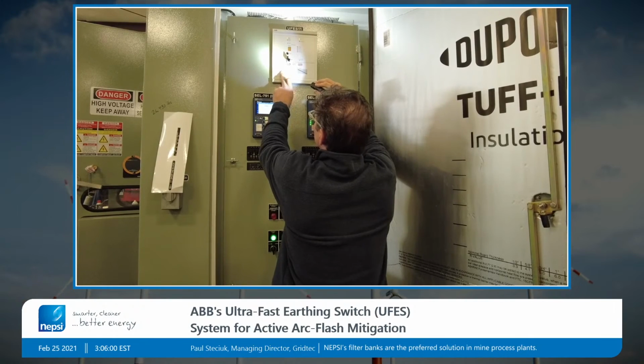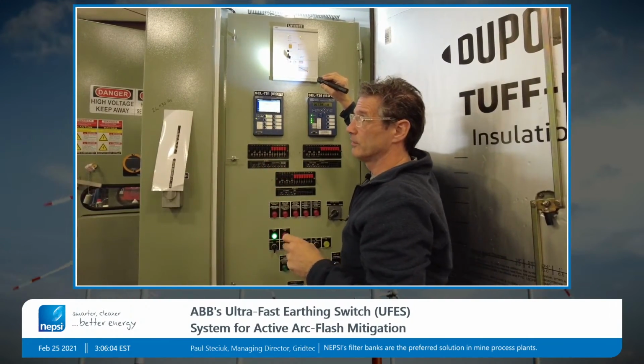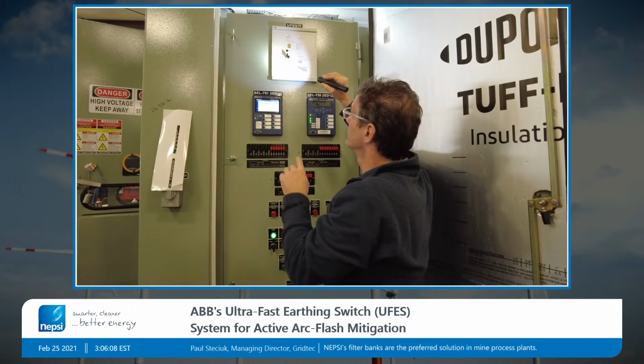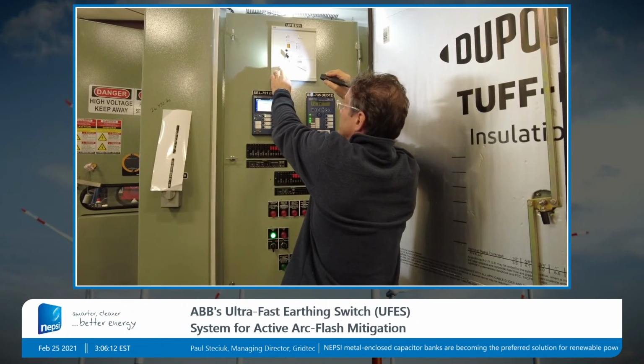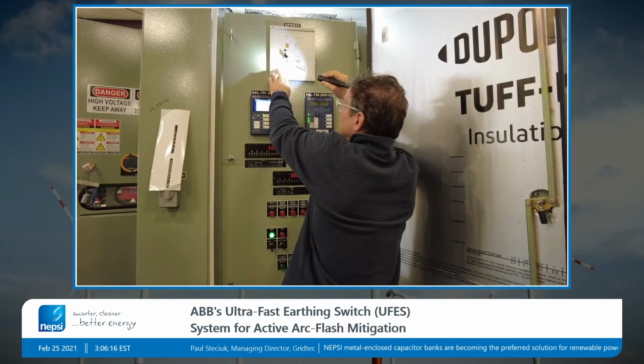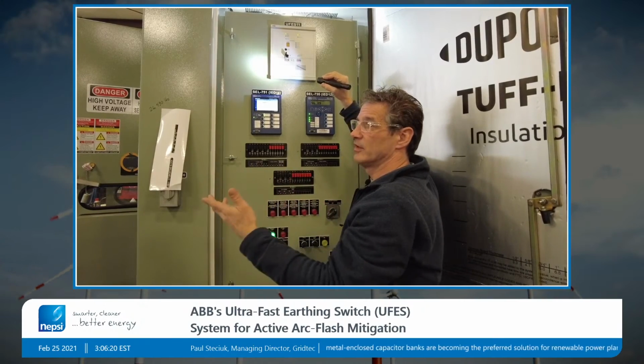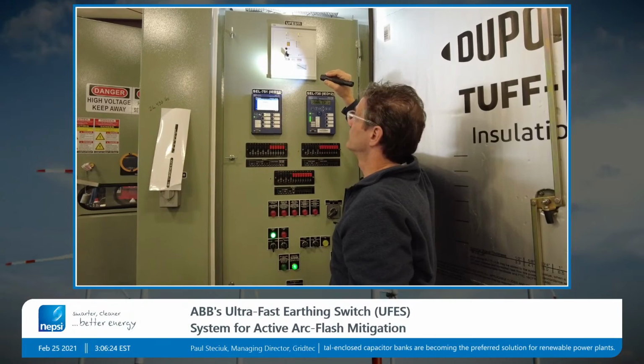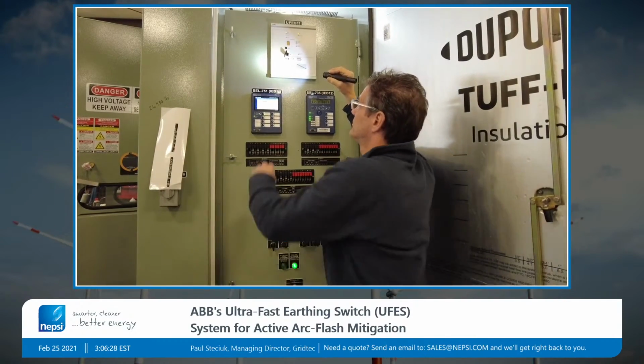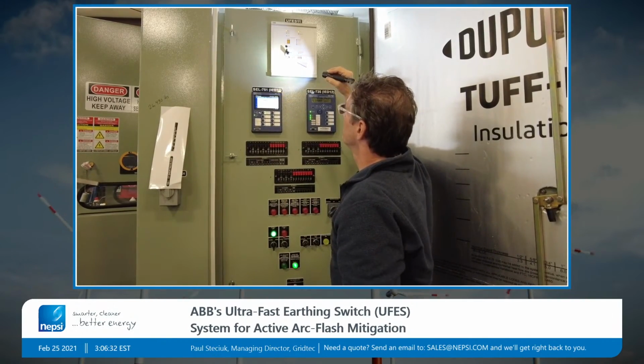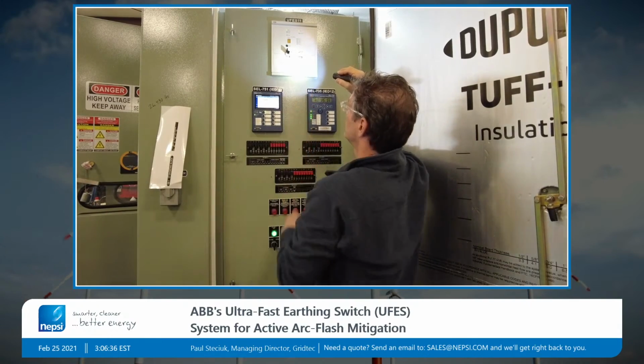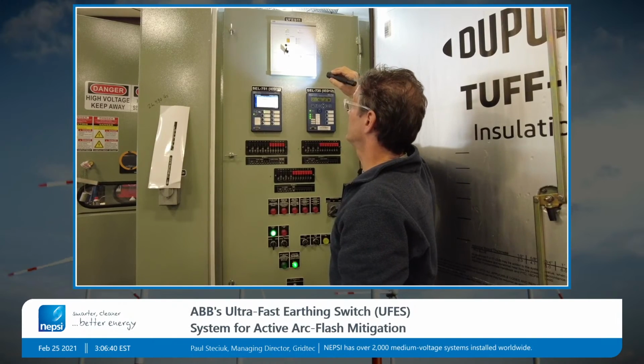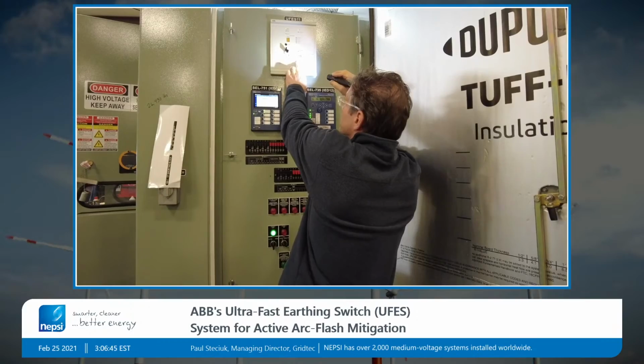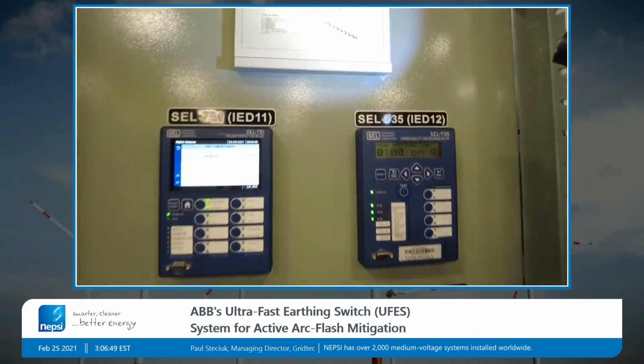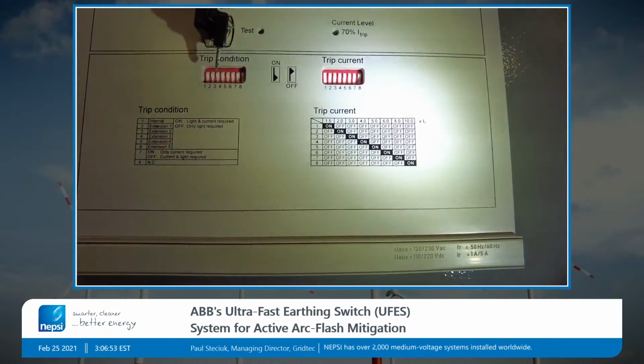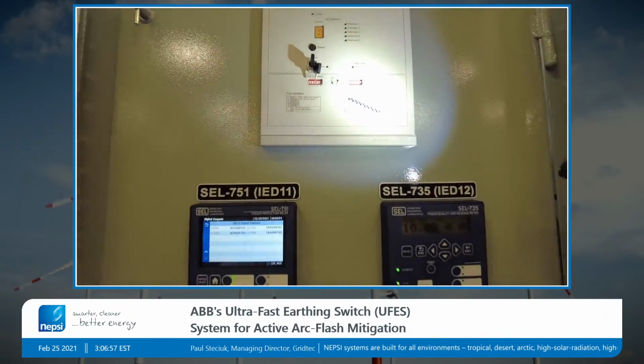There are other extensions, extension 1, 2, 3, 4, and 5. If you had multiple other light sources that are through a relay, you can send those additional inputs into these extensions. Would it be like a 751A, for example, aux? Or it has to be something that sends out a signal that would be able to be read by this. Okay. We have not used options 2, 3, 4, and 5 here. And for trip current, it's just dip switches. It's kind of like a binary. We normally set it on the lower side. For our project here, the trip current is 1.5 amps times IR, where IR is a 5 amp secondary CT. So we're tripping at 1.5 amps times 5 for our trip current.